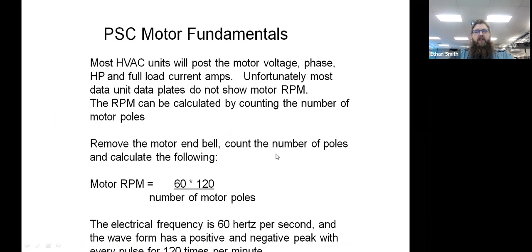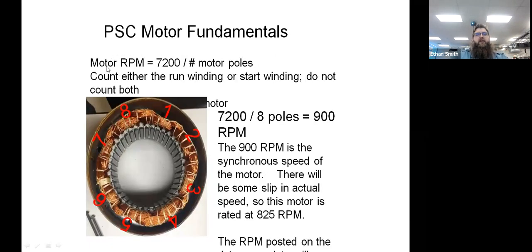One of the interesting things about this is if your motor is all shredded out and you don't have the labels on it, you can actually figure out what the RPM of your motor is. You can do that by counting the number of poles or windings. In that motor we just looked at, we had 8 poles, 8 run windings on it. And you can take that and do some math. We've got a universal constant, which is 7,200. That's what you would get on a motor if you only had 1 pole.